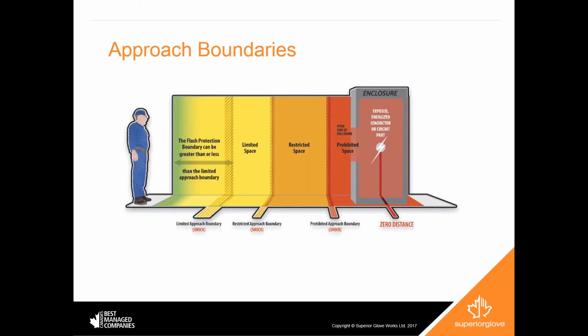And this boundary is determined by NFPA, the National Fire Protection Association, in their standard NFPA 70E, and it's based on the voltage of the equipment. Now, these distances aren't going to be consistent between every piece of equipment. Some equipment will have a greater flash protection boundary, while other equipment will have less of a protection boundary. So it really depends on the voltage that you're working with. And so Robert will talk a little bit to us about selecting the appropriate PPE.